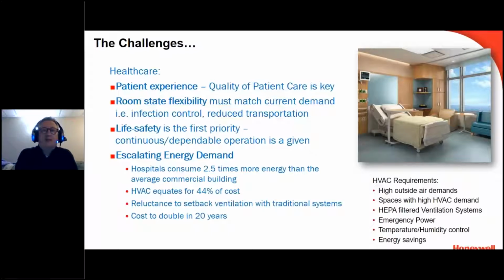And so what we're seeing over the last few years is the need for multi-use capabilities, right, or room state flexibilities. And we'll dig into that a little bit more, but this is one area where I think it even becomes more apparent given the pandemic, is that many of these spaces in the hospitals are not able to be used, right, as pandemic ready because of maybe an aging infrastructure or the mechanical performance isn't quite there where it needs to be. And by using Phoenix controls and the Venturi valve, we do give you a little bit more flexibility in order to take that room and turn it into a procedure room or create a better environment for better safety and patient care for those particular applications that are going on. It's very different how the building was being designed versus how it's being currently used today. And so there's a gap there, I think, that we can kind of help close in.